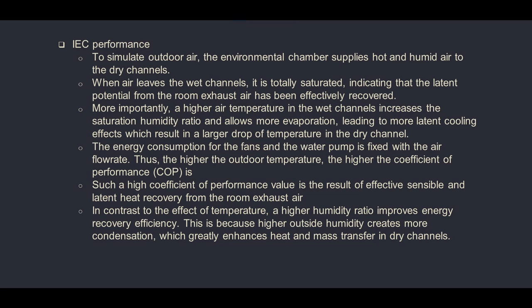The energy consumption for the fans and water pump is fixed with the air flow rate. Thus, the higher the outdoor temperature, the higher the coefficient of performance is. Such a high coefficient of performance value is the result of effective sensible and latent heat recovery from the room exhaust air. In contrast to the effect of temperature, a higher humidity ratio improves energy recovery efficiency. This is because higher outside humidity creates more condensation, which greatly enhances heat and mass transfer in dry channels.